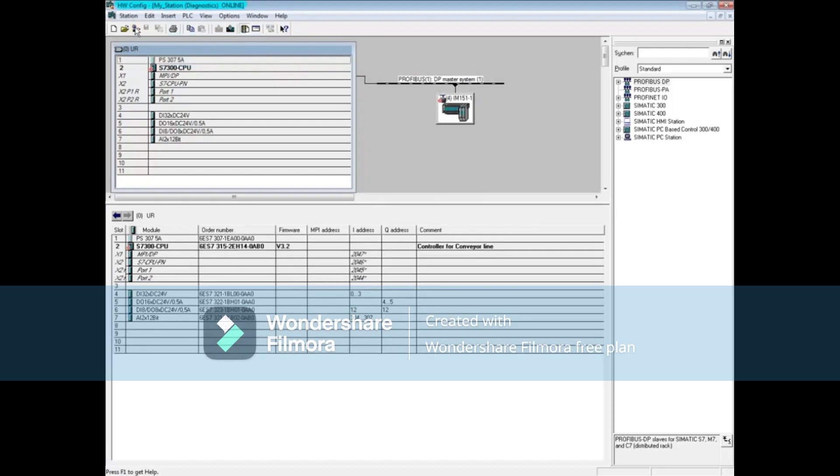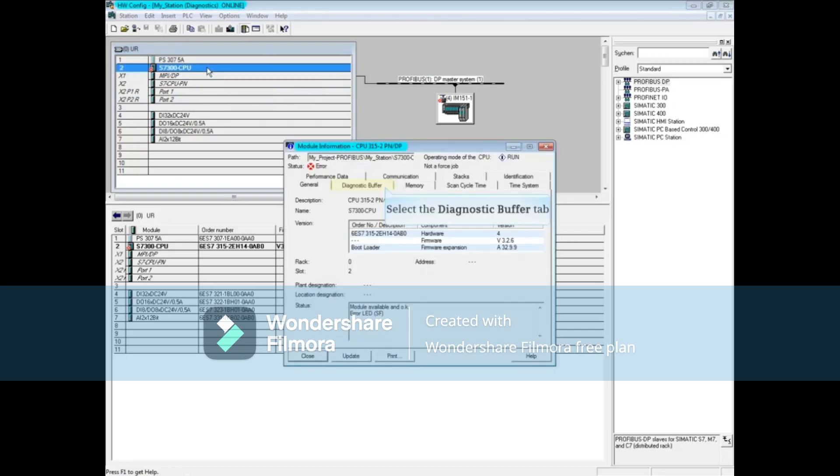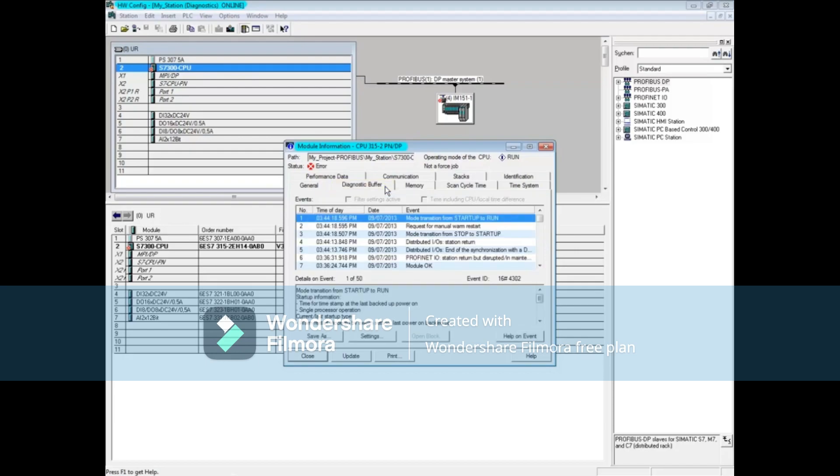The red marks indicate a fault with the CPU and the ET200S station. While online, double-click the CPU to open the module information tool. Click on the diagnostic buffer tab. There is no relevant information here, so let's go to the station diagnostics.